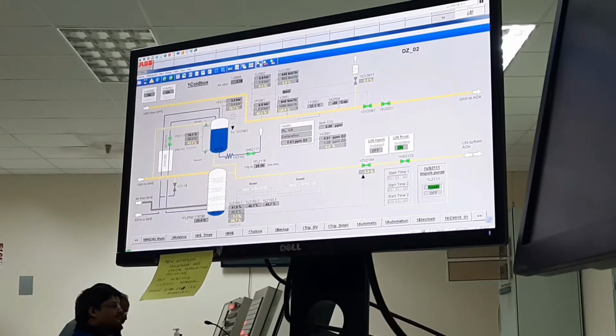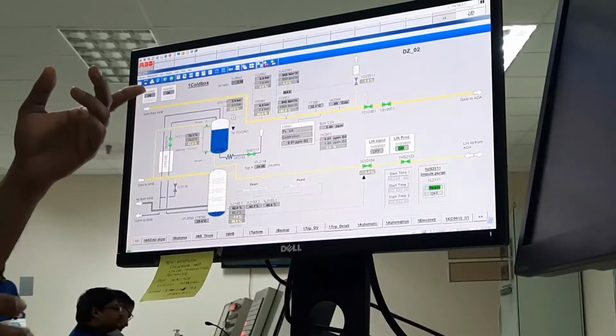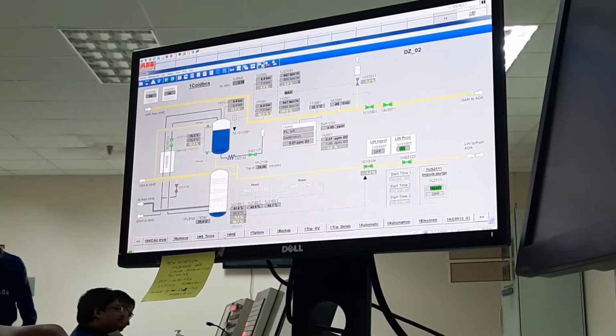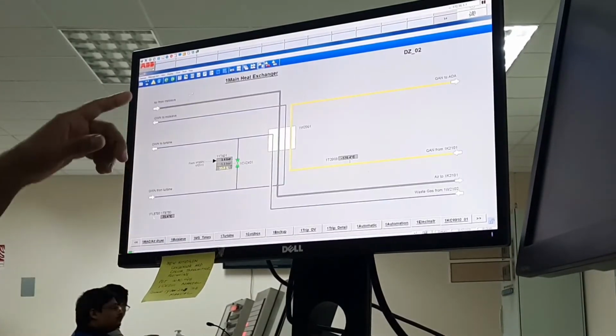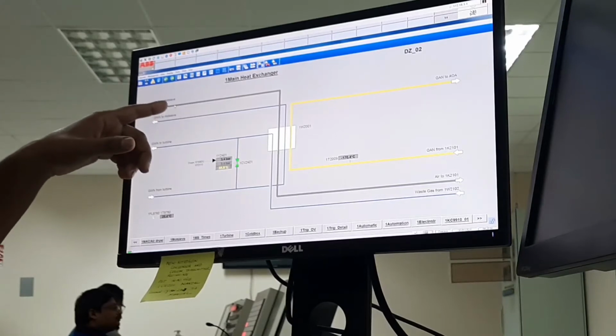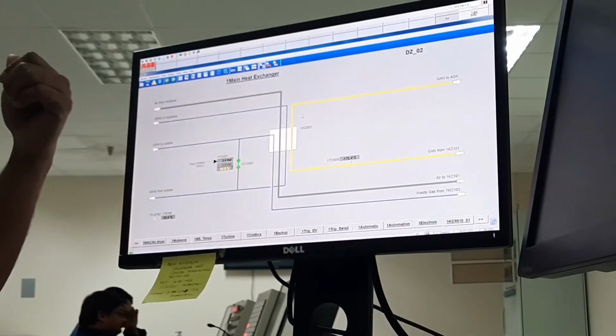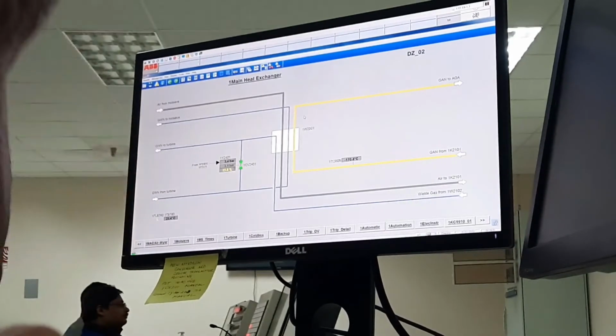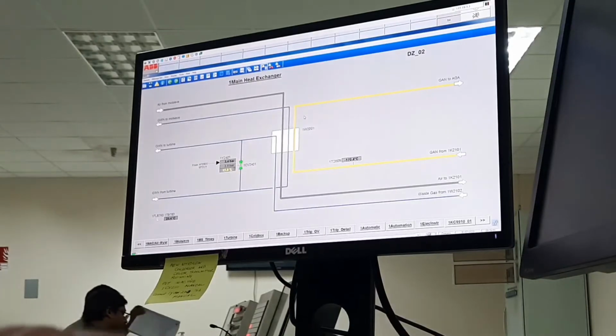Any question about the gaseous product? This temperature is 32. No problem, 32 sometimes. It depends on the heat exchanger side. If this temperature sometimes comes at 35 or 38, take it that it is from the air dryer. When the temperature coming from the air dryer is higher, at that time this outlet temperature is also higher.